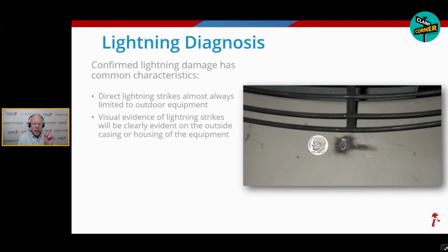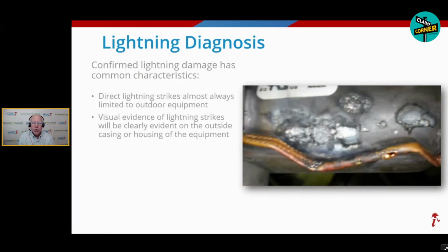This one hit the cabinet, jumped down about 6 to 8 inches, and hit the reversing valve. This is a heat pump. Heat pumps have reversing valves. Reversing valves have low voltage solenoids in them to change from air conditioning mode to heat pump mode. Look how much energy jumped down through free space, right? It melted that solenoid and opened up that refrigerant line. See the hole in that copper line? All the refrigerant leaked out as well.